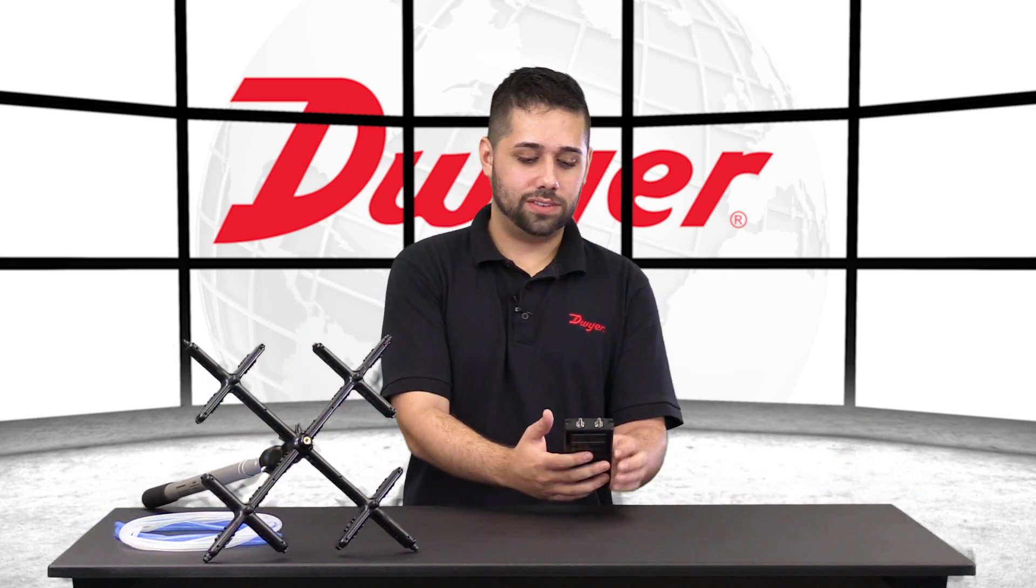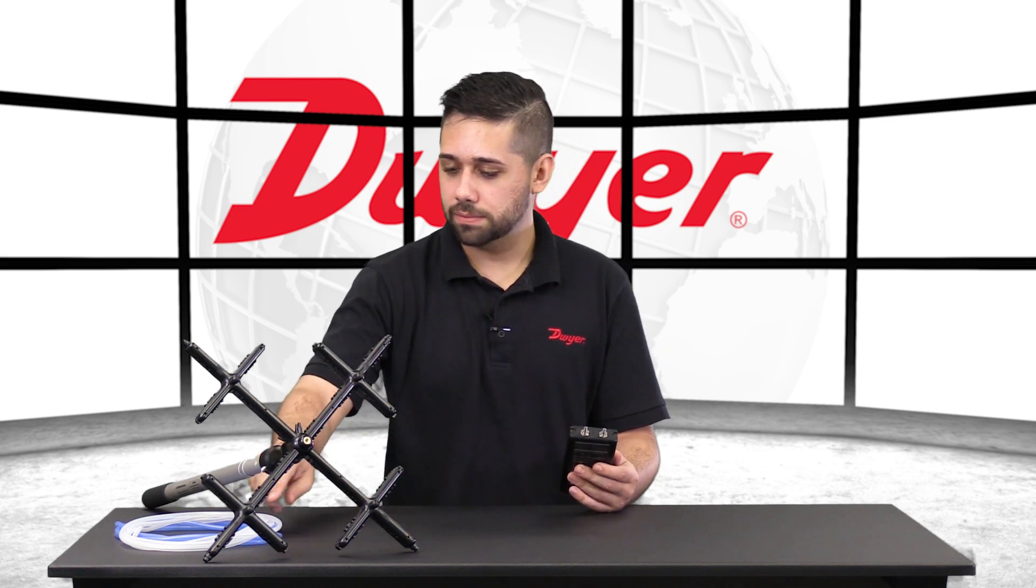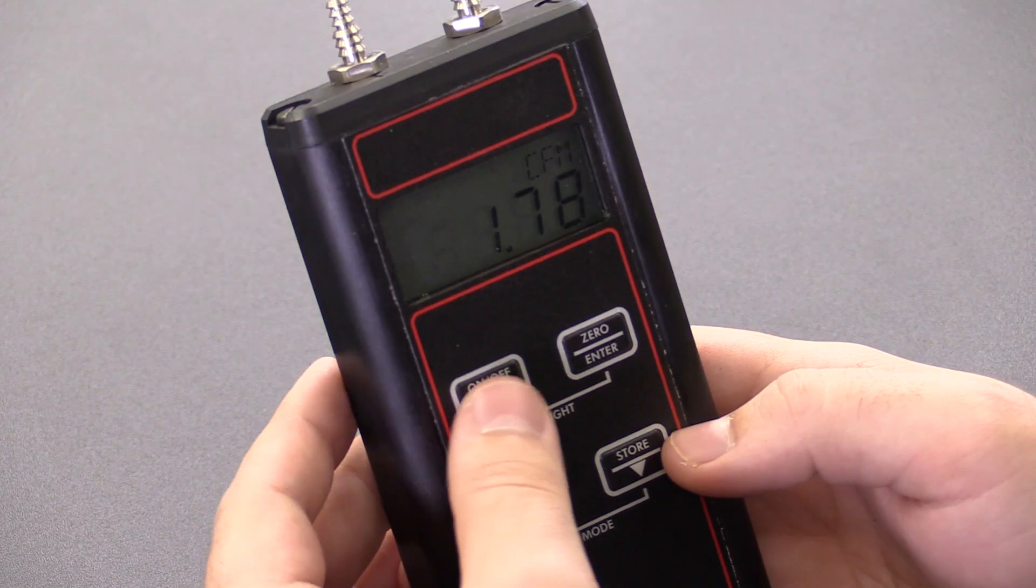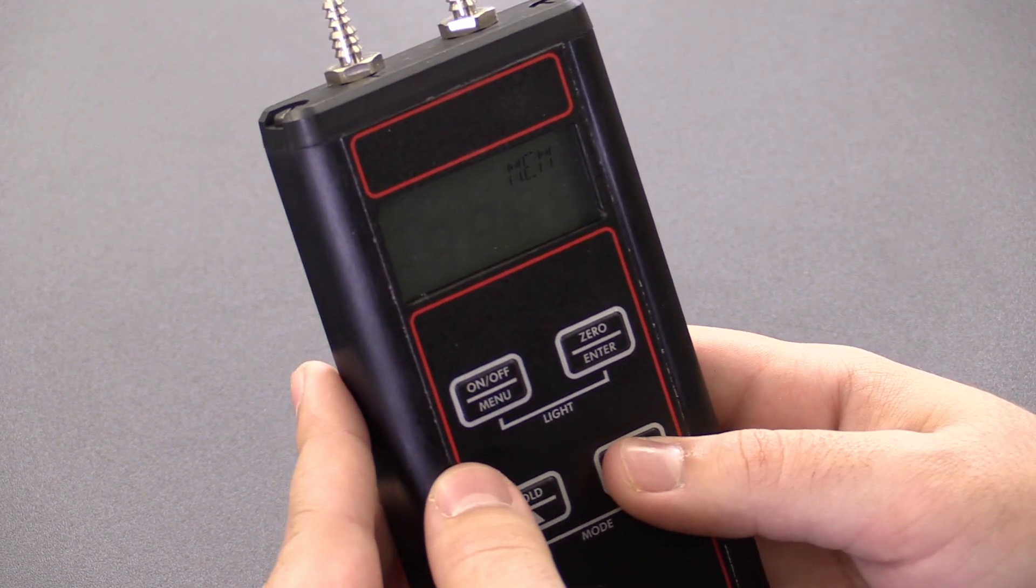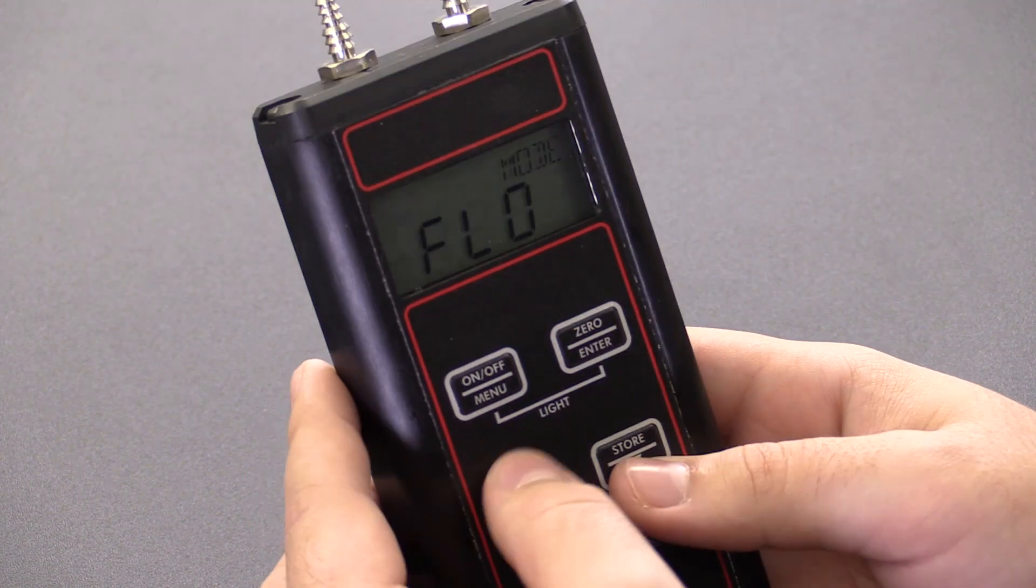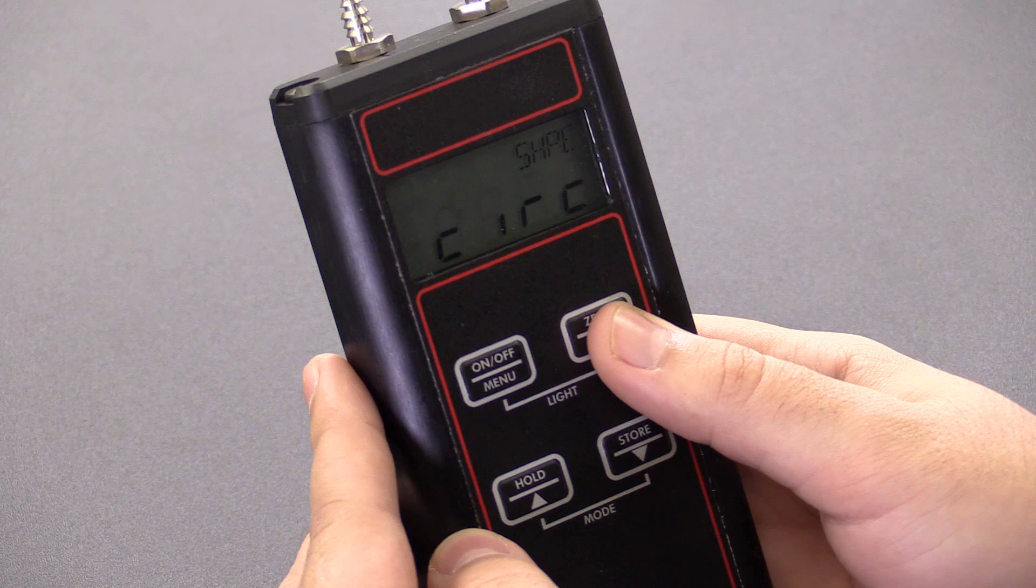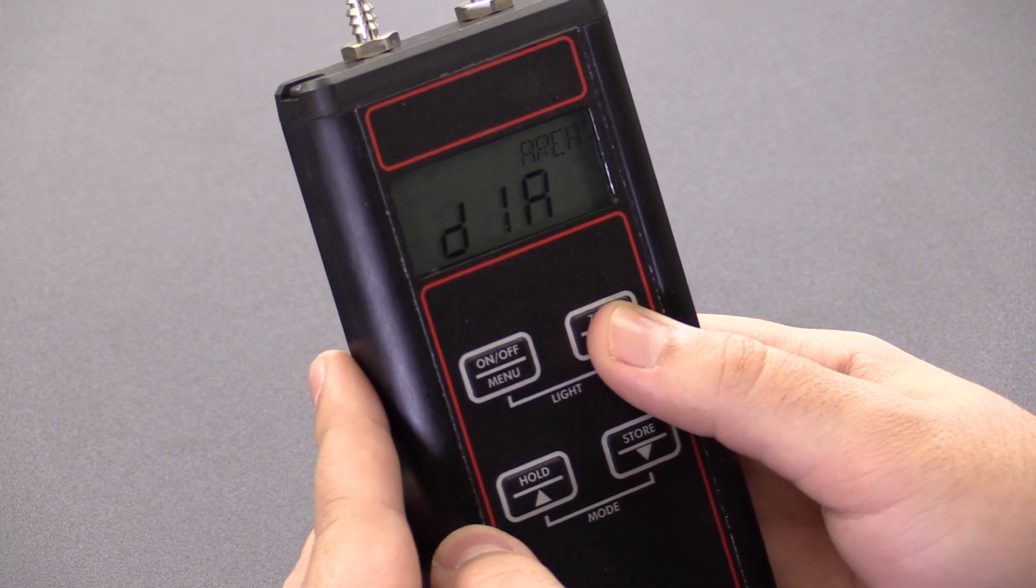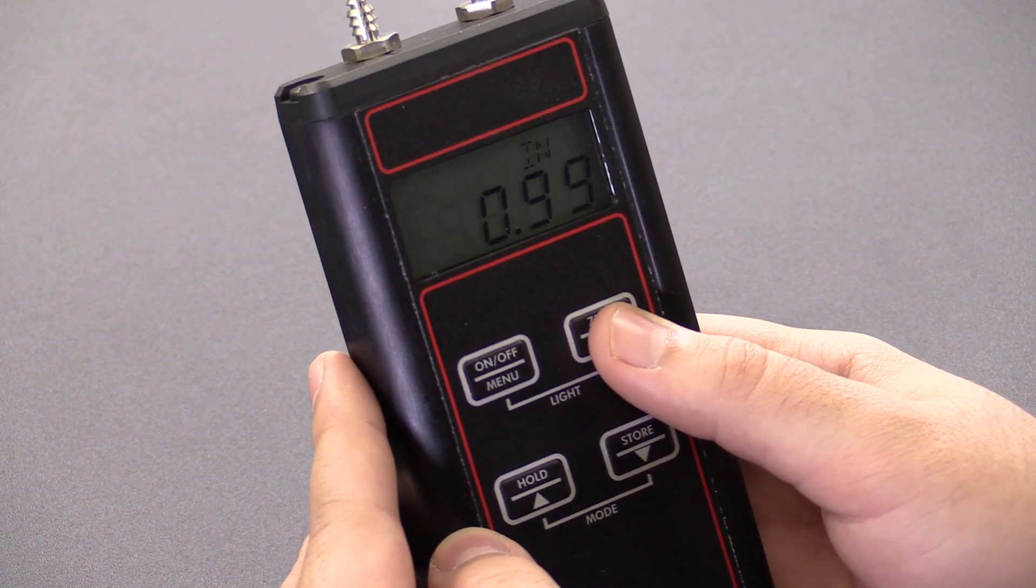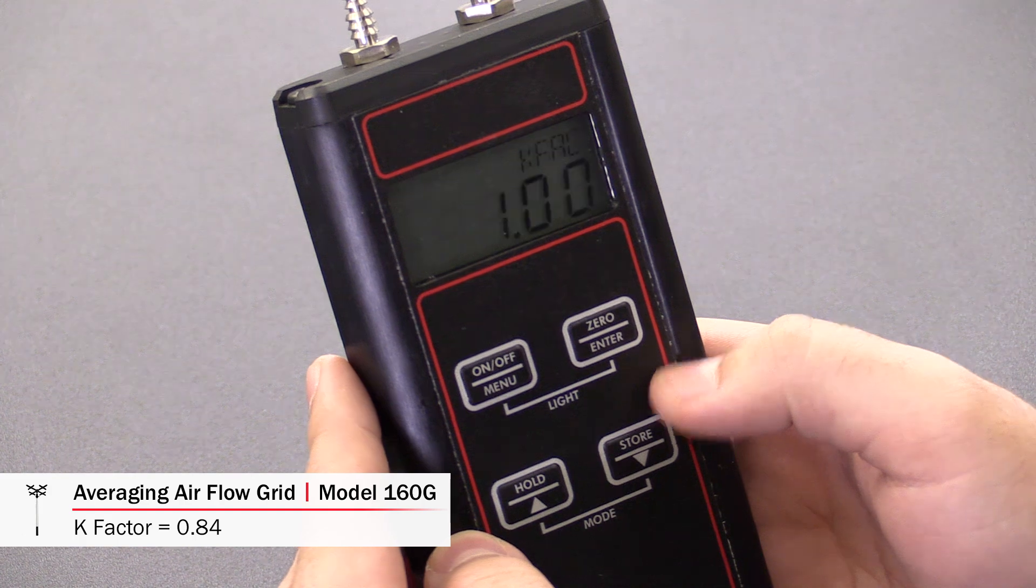Next, let's connect the 477AV to the 160G. First, we'll need to adjust the K-factor to match the air grid. Just go into flow mode once more. We can keep everything else the same. The K-factor's got to go to 0.84.